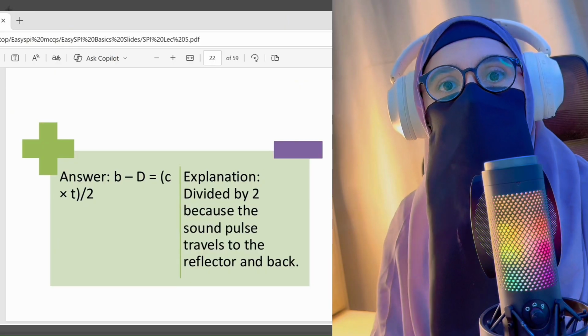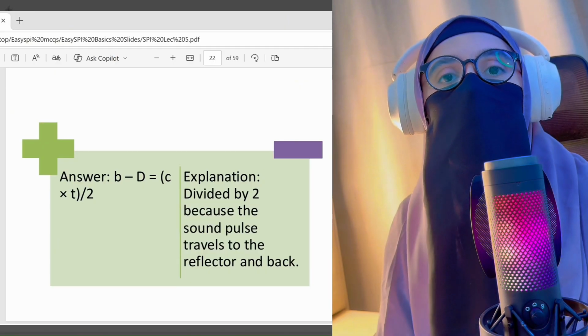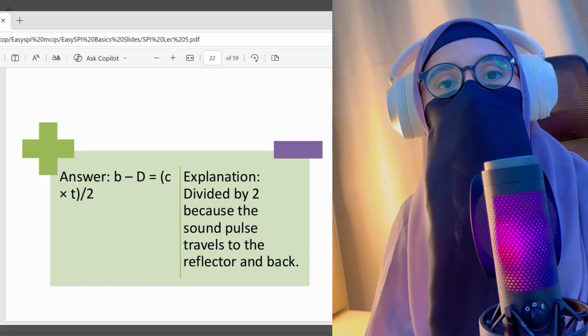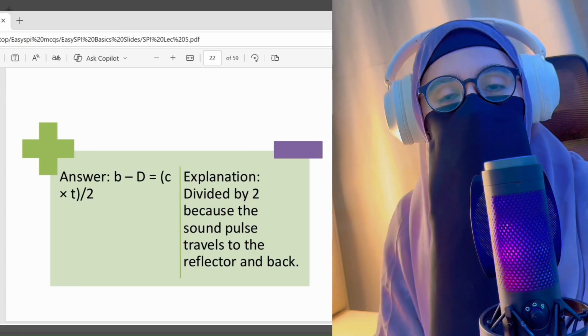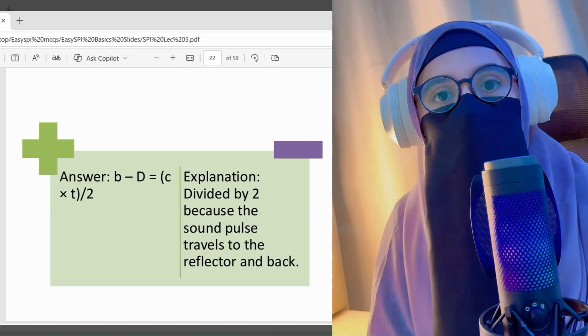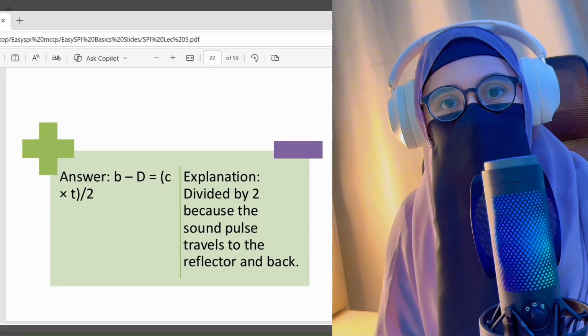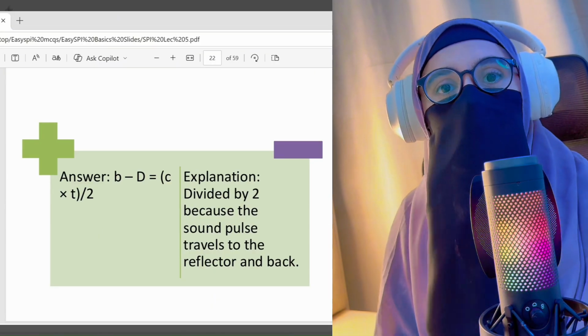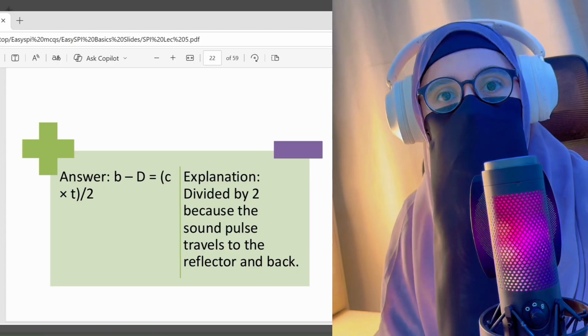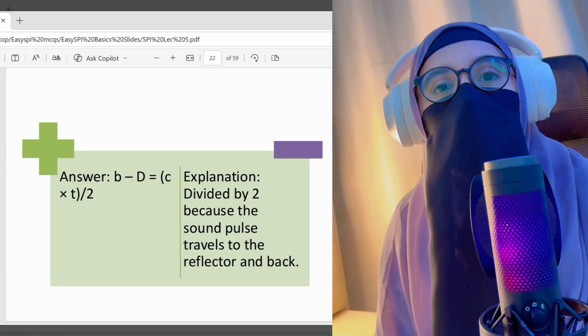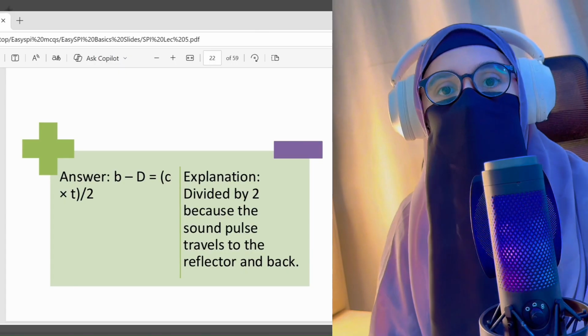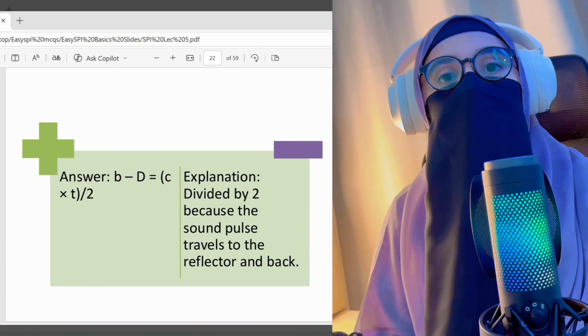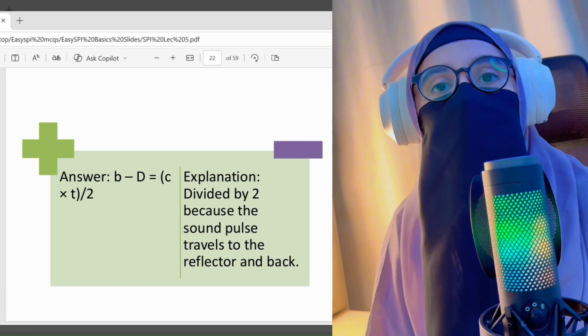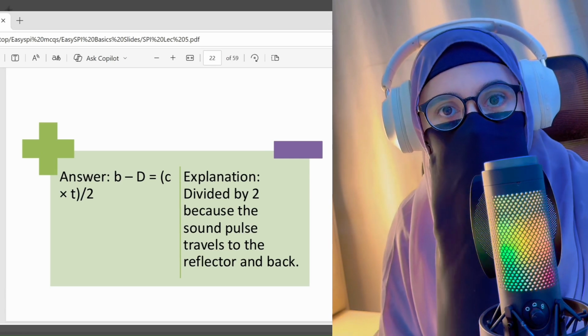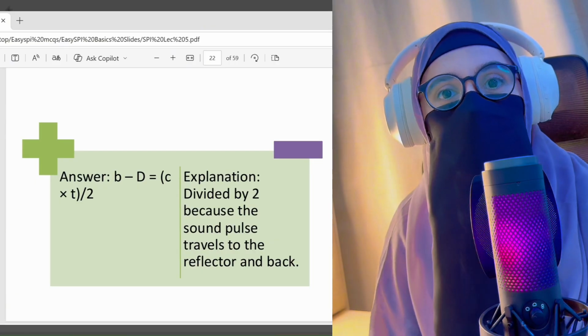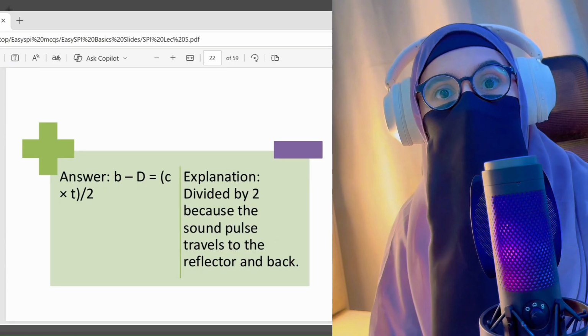Next, the correct range equation is: depth is equal to speed of sound in the soft tissue multiplied by go return time, divided by 2. Why divided by 2 here? Because go return time is the total time. The pulse takes to first transmit and then come back to the transducer. But for the calculation, we only need one-sided time. That's why we divide by 2. And the speed of sound in soft tissue is a constant value, 1540 meters per second or 1.54 millimeters per microsecond, which is known as the calibration speed.